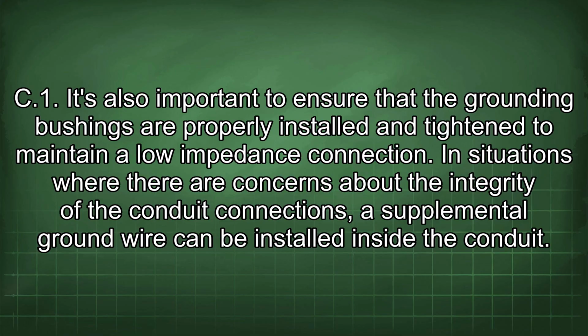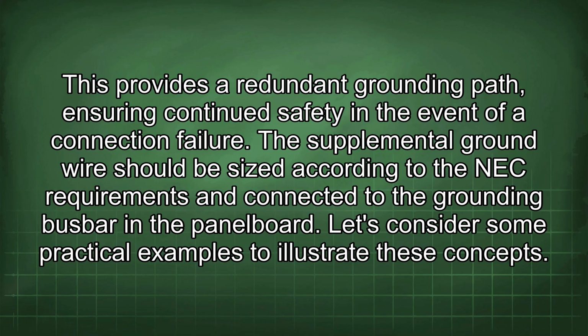low impedance connection. In situations where there are concerns about the integrity of the conduit connections, a supplemental ground wire can be installed inside the conduit. This provides a redundant grounding path, ensuring continued safety in the event of a connection failure. The supplemental ground wire should be sized according to the NEC requirements and connected to the grounding busbar in the panelboard. Let's consider some practical examples to illustrate these concepts.